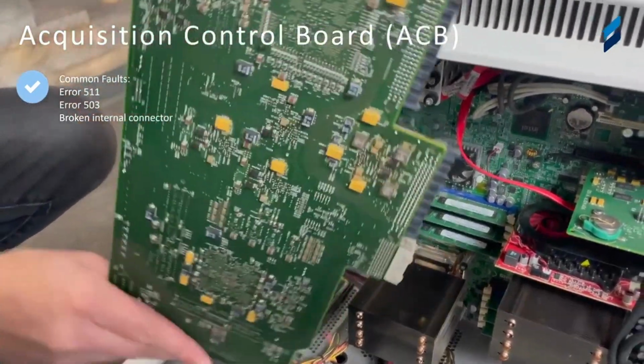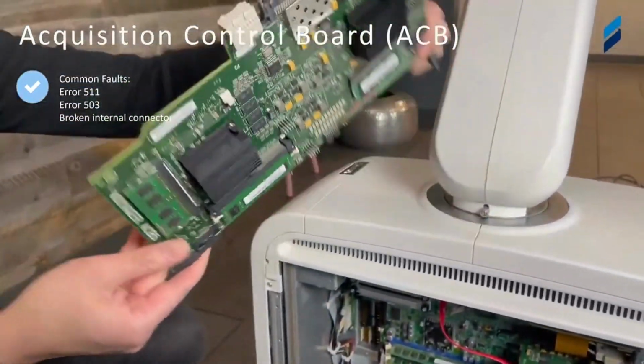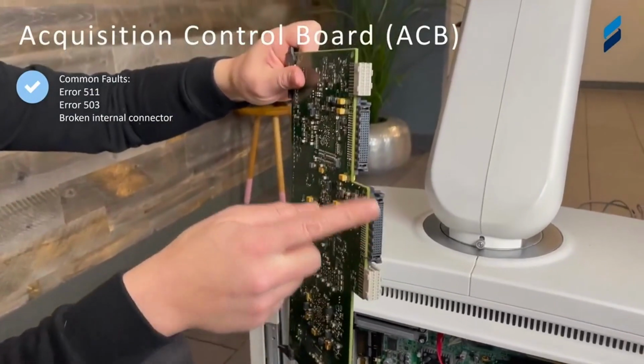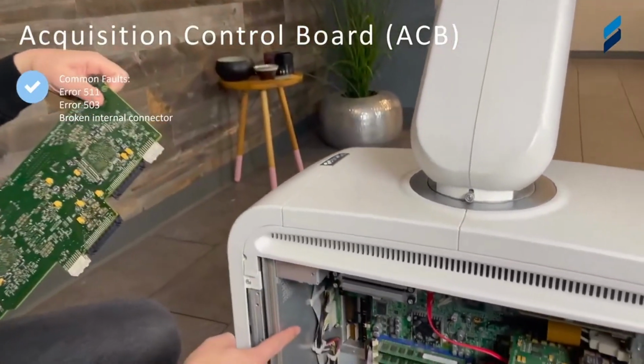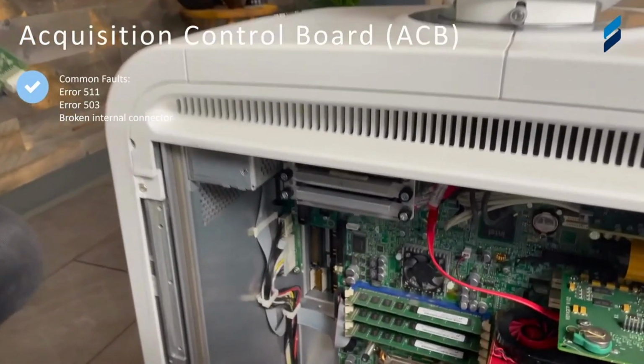So we had already removed the power regulator. Now we're going for the ACB. The function of this board is controlling the acquisition module. It's also the main beamformer. It takes all the information from your acquisition module that it sent and received to the probe, and now it's ingesting it and pushing it to the processing unit, which is the computer here, or the Ebox.